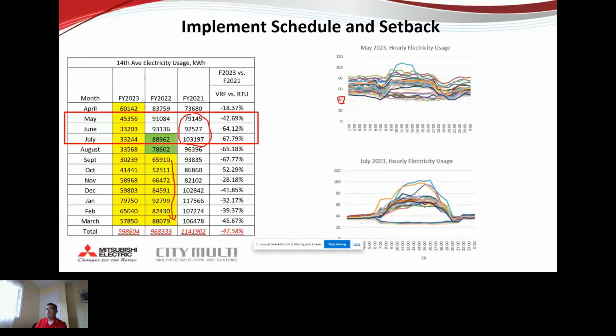But once we switch into scheduling, the weekend is pretty much just setback and shut off. During nighttime, we also have a setback, using ERV to bring in cold outside air, as well as purging the office first thing in the morning. So you can clearly see the difference between unoccupied and occupied hours, and after everybody goes home, as well as on weekends.